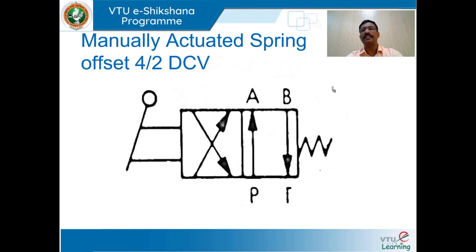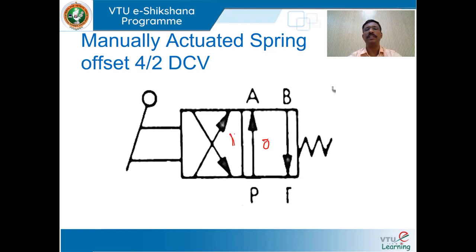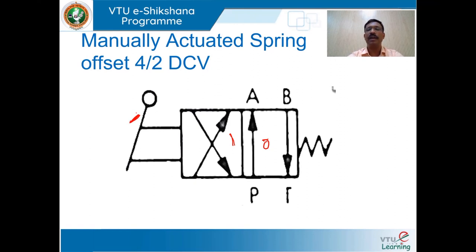We shall draw a symbol for a manually actuated spring-offset four-way two-position directional control valve. Two-position is denoted by two adjacent squares — position O and position 1. A lever is shown on one side and a spring on the other side. In the spring-offset mode, P is connected to A and B is connected to T.